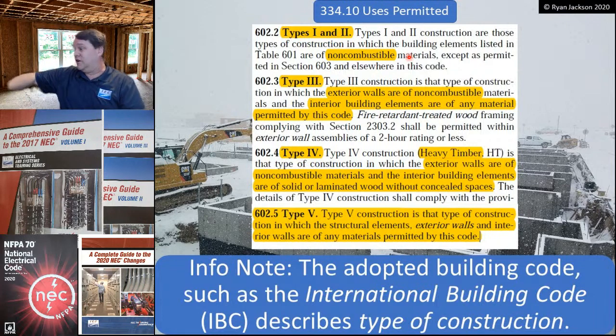You can have combustible wood handrails or cabinets, stuff like that, but we really limit how much combustible stuff you can have in a non-combustible building. Can't have combustible wiring methods in a non-combustible building. That's the idea here. Type 3, 4, and 5, you really don't have to get into the differences between 3, 4, and 5, because for our application, the rules are the same. You can use it in type 3, 4, and 5. You can't use it in types 1 and 2. So really, all you need to know as an electrician is that types 1 and 2 are totally non-combustible.